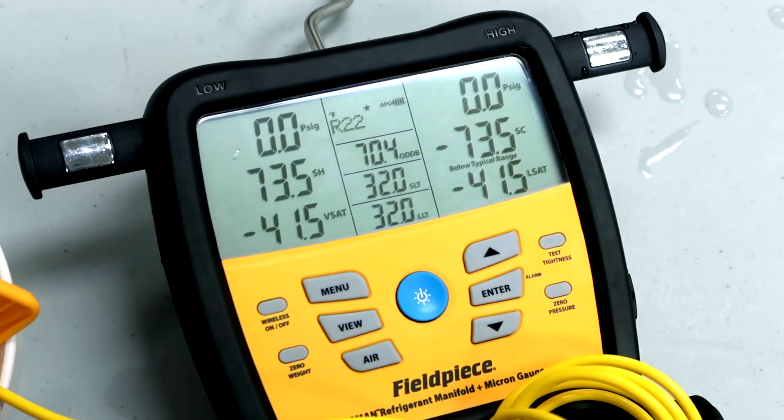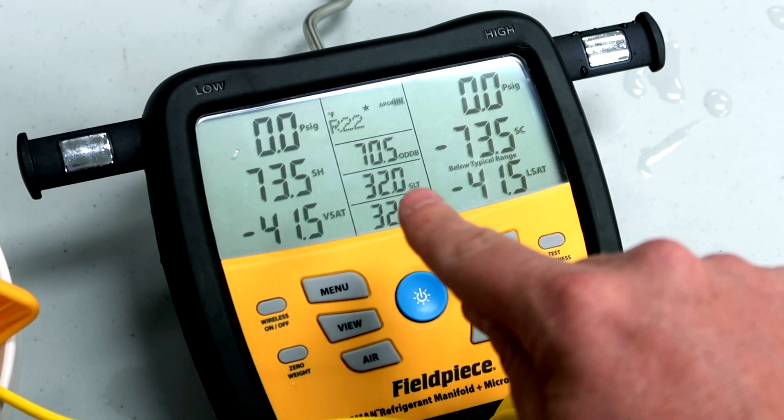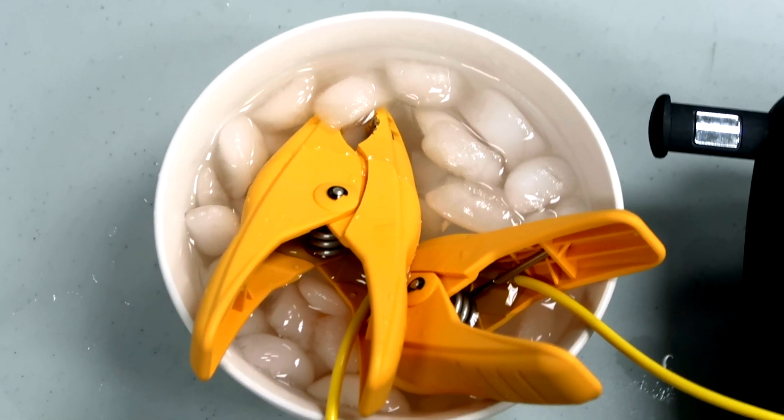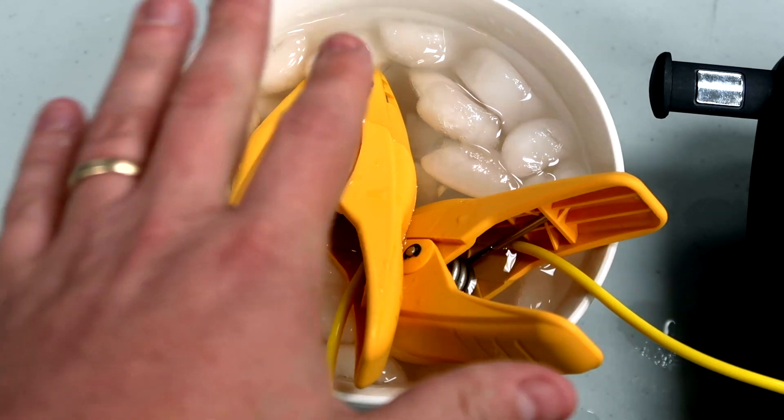When we're done, all we do is hit menu and that goes back to the beginning. Making sure that you're calibrated to a known temperature—in this case water at saturation when it's melting, 32 degrees—that's what we're calibrating to.